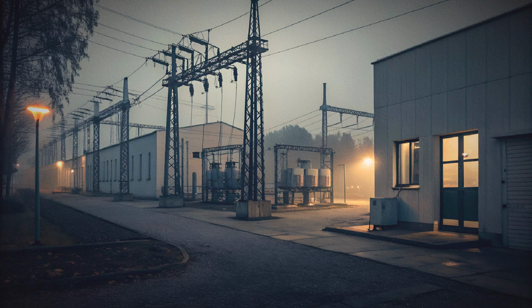Grounding, or earthing, is another fundamental element. Proper grounding provides a reference potential for the electrical system. It reduces the risk of uncontrolled voltages during faults. Grounding systems connect equipment frames, neutral points, and ground grids to dissipate fault currents safely into the earth. Substation grounding design considers soil resistivity, fault current magnitude, and operator safety protocols. Grounding also supports coordinated protection schemes by providing predictable paths for fault currents.